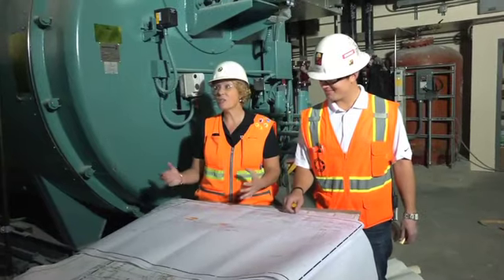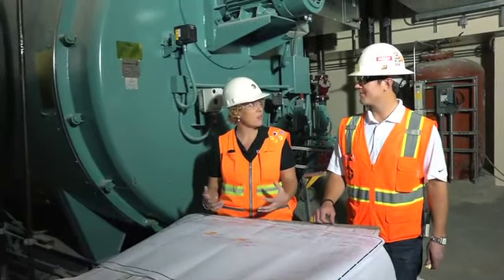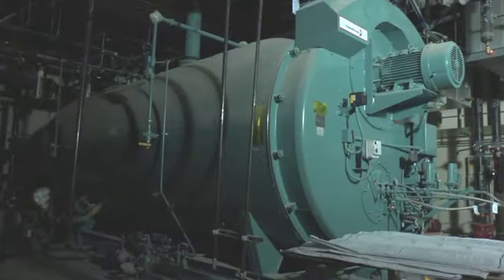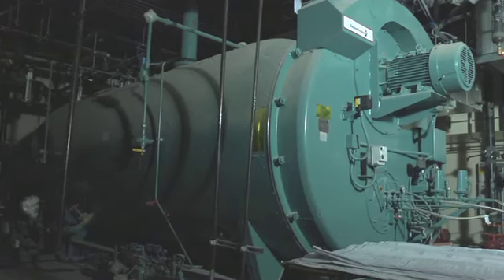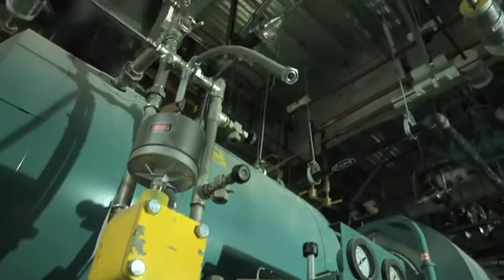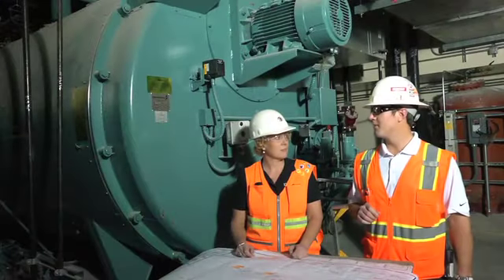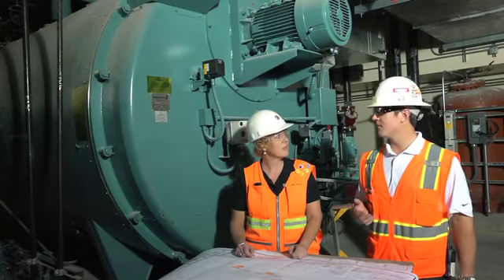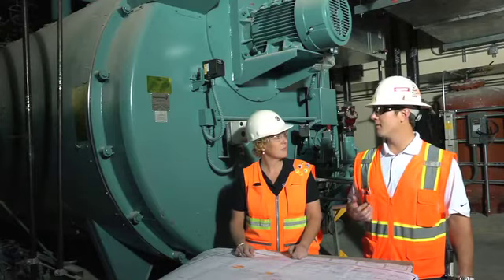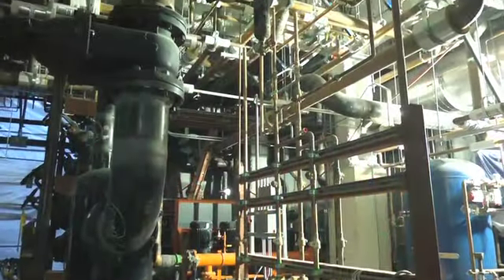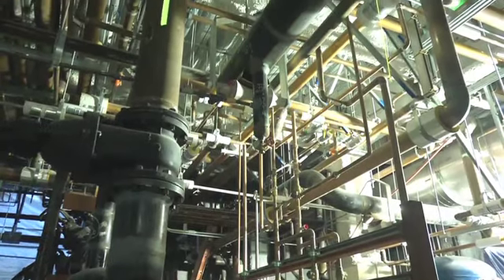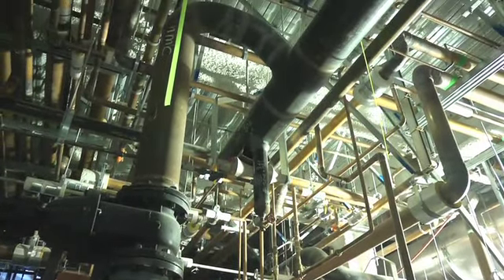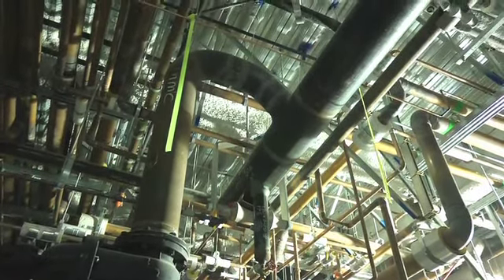Ben, these are some of the largest boilers I've ever seen. Can you tell us a little more about them? We have 2 400-horsepower boilers. Each boiler is capable of producing 13,800 pounds of steam per hour, which produces steam for all the sterilizers, the heating and cooling, and all the hot water systems throughout the building.